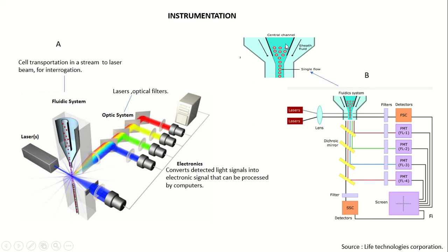in figure B, upper left hand side. This stream that I am talking about, this single flow, is maintained in traditional flow cytometry by using the property of hydrodynamic focusing, which means our single cell suspension, or the sample, is injected in the core part. Imagine a very narrow quartz tube into which our single cell suspension is injected.